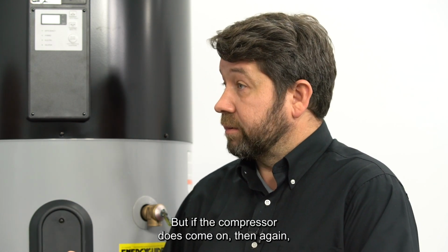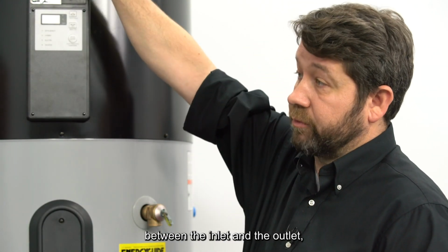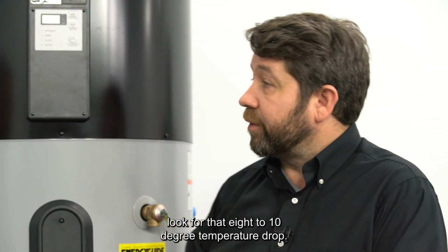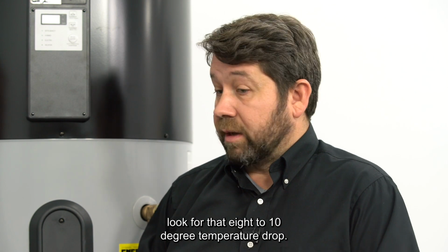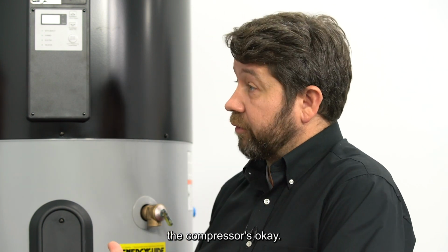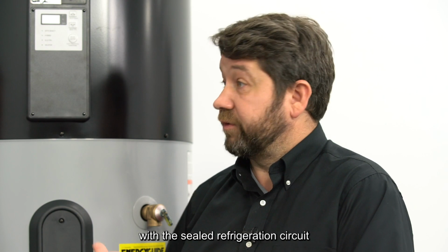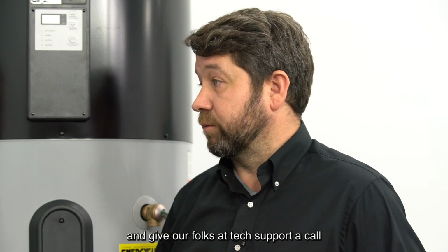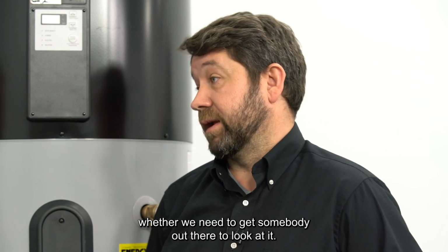But if the compressor does come on, then again, we're going to check for that temperature drop between the inlet and the outlet. Look for that 8 to 10 degree temperature drop. As long as we see 8 to 10 degrees, the compressor's okay, but if we don't, that indicates a problem with the sealed refrigeration circuit, and give our folks at tech support a call so that they can determine whether we need to get somebody out there to look at it.